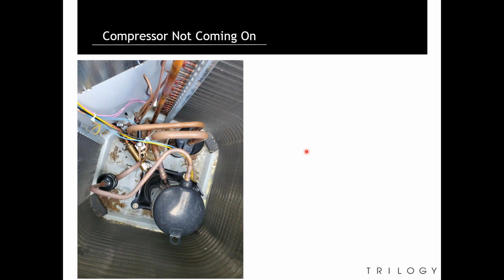So if the compressor is not coming on, do we have voltage from the contactor? We want to make sure that we have 240 volts coming from the contactor. Is the capacitor working properly? Again, that capacitor is a problem. So check the capacitor. Make sure you're getting the correct microfarads. If it's a 35 by 5, you need 35 for the compressor, 5 for the fan.